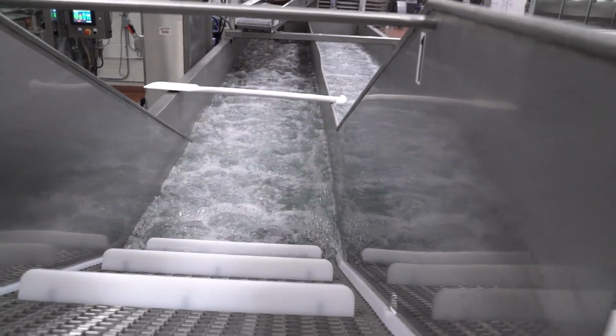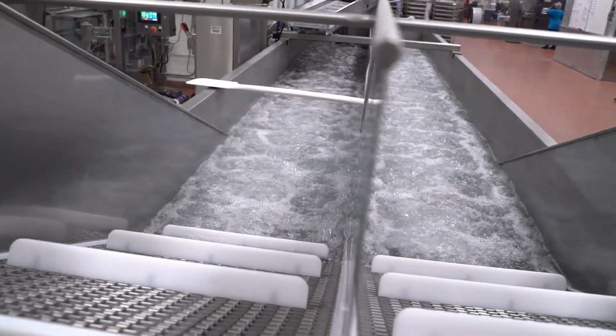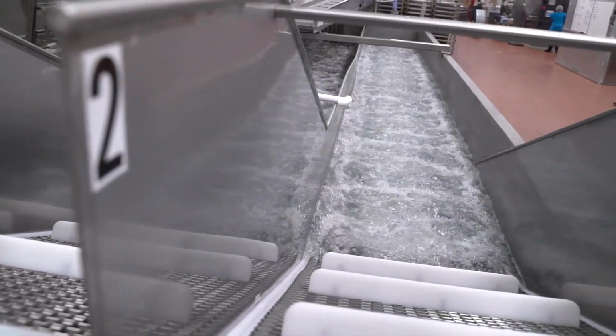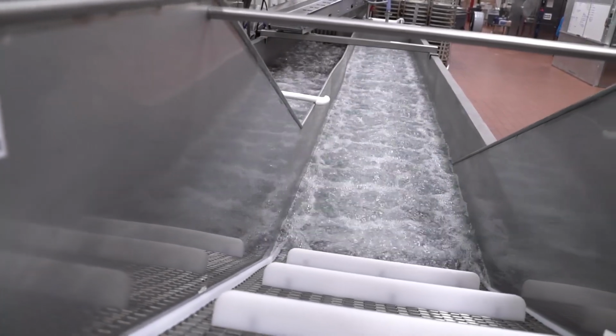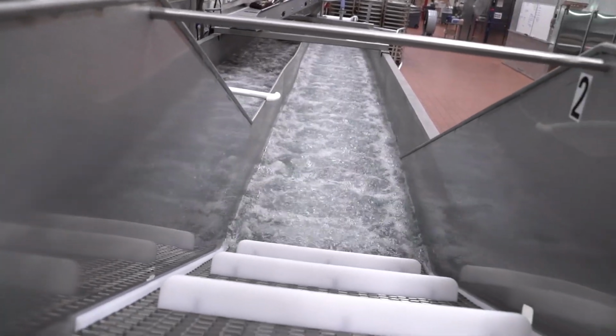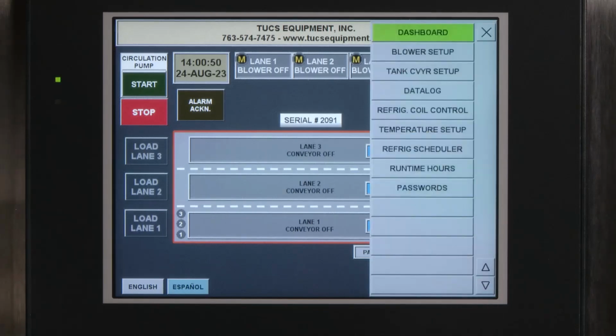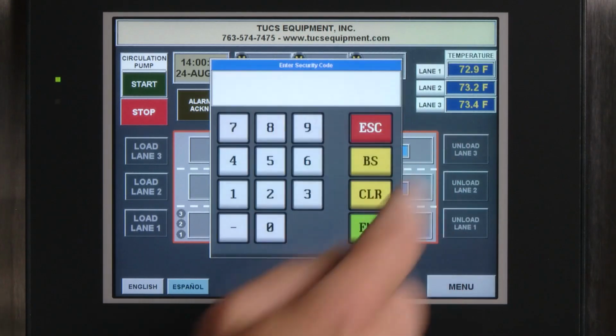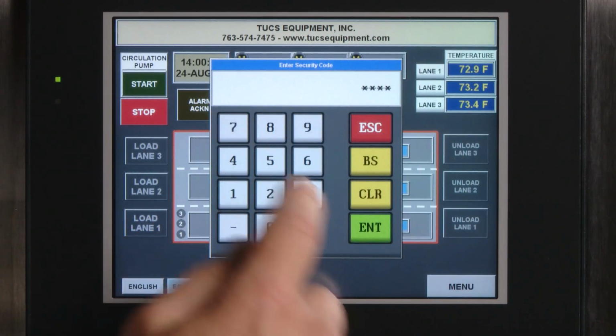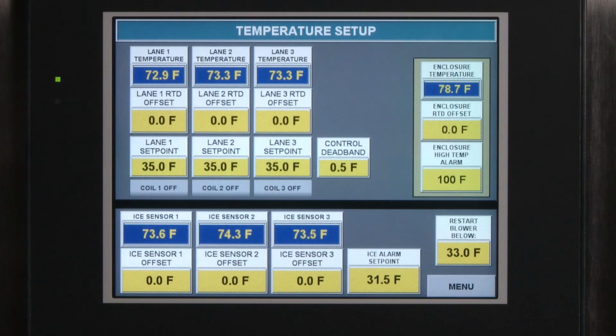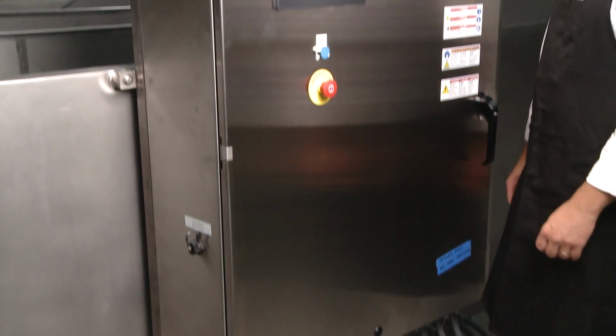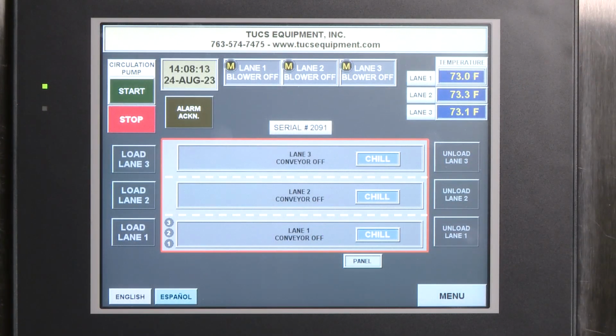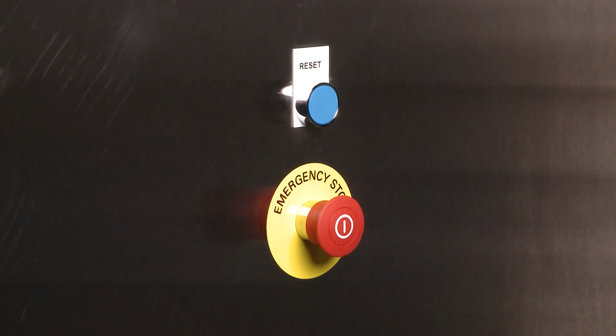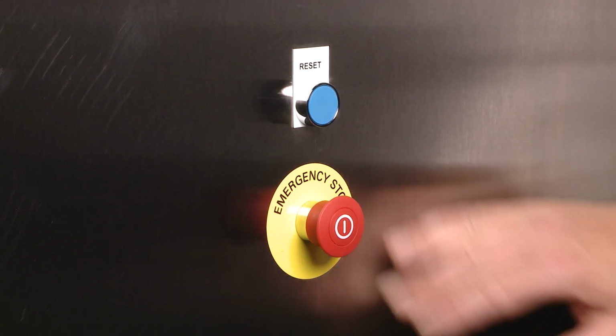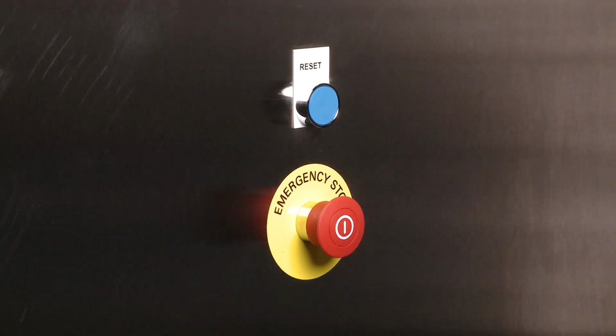Cold-flowing water can slow bacteria from developing. Therefore, the chiller must run at all times with the water circulation pump on and the refrigeration enabled. The water temperature is set at initial setup and kept the same, so there is no need to adjust it. On the side of the chiller is the control panel that includes the HMI, or Human Machine Interface, and 2 manual buttons, the E-Stop button and a Reset button.